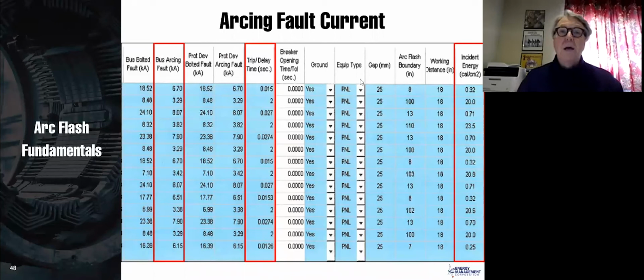That's great. Let's take a look at line 2. Line 2, our fault's only 8 calories. So clearly that's less dangerous, right? This is only 8,000, did I say calories? I'm sorry. This is only 8,000 amps, whereas the line above it was 18,000 amps, so clearly a much safer circuit. The arcing fault is only 3,000 amps. That's less than half of what this arcing fault is, so that looks like it's going to be much safer. But let's go over here, and it's got 20 calories. Whoa! Why is that 20 calories? It's not safer. It's much more dangerous.